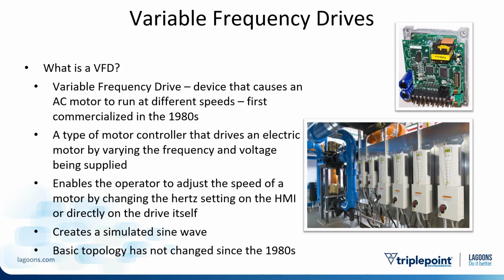A variable frequency drive, or a VFD, is simply a device that causes an AC motor to run at different speeds. They've been around since the 80s. What they do is drive that electric motor by varying the frequency and the voltage being supplied to it. That enables the operator to adjust the speed of a motor by changing the hertz setting on a human-machine interface or directly on the drive itself. If your drives are tied into a SCADA system, you can probably ramp them up and down using SCADA. A little bit later in the presentation, I'll talk about an automated approach using DO control in the effluent.